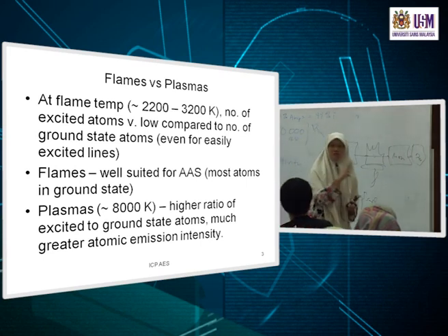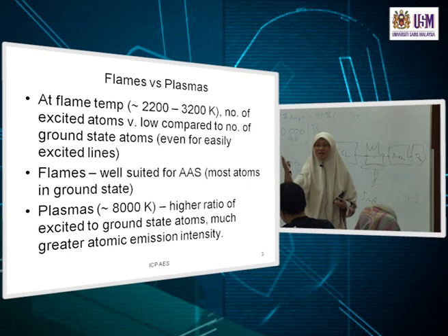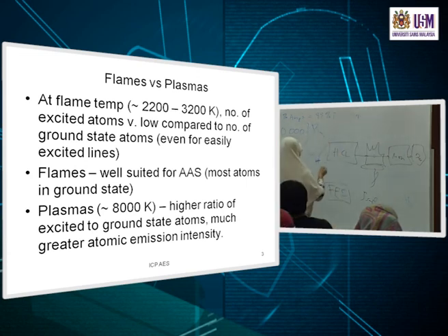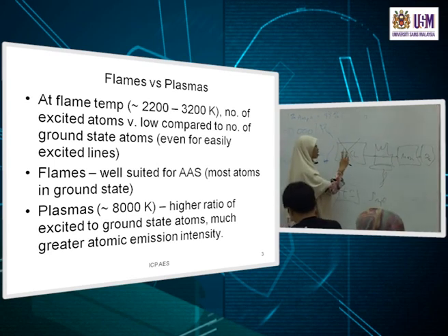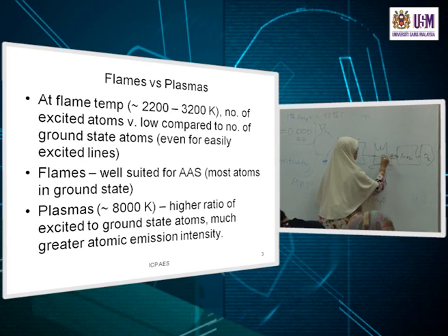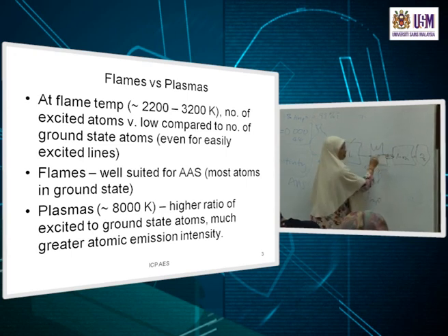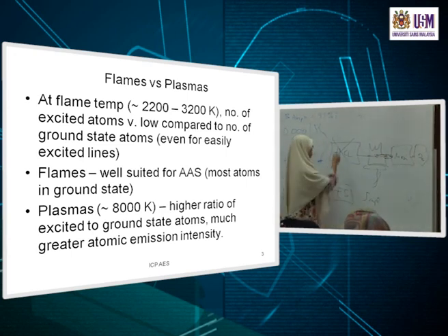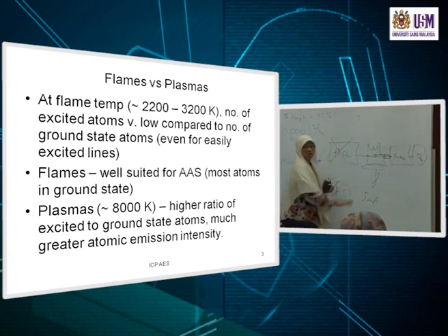I heard someone say something there. What did they say? The source, okay. No need for the source. Because why? We are not measuring how much light is absorbed. We want to know how much light is given out by these excited atoms in the flame. So, no need for the source. Same equipment but just used for flame emission.